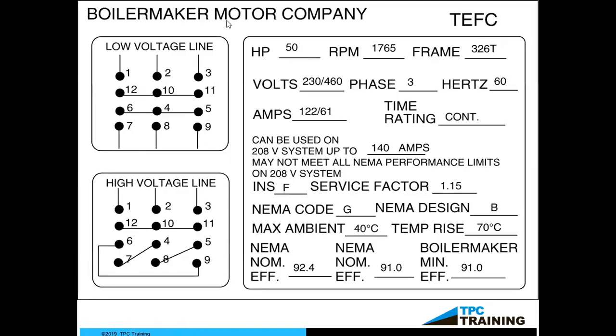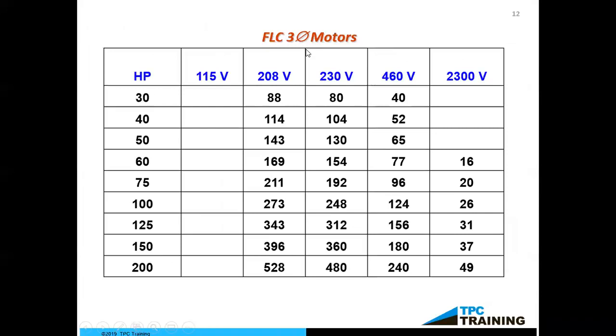So I did say that I wanted you to really think about this FLA, the 61 amps at 460 volts. Remember, it is a 50 horsepower motor, because the next slide that I have does not say FLA at the top. It says FLC. So the FLA that we saw on the motor, the 61 amps, that's full load amps, comes right off the motor nameplate. This is full load current, and it comes out of the National Electrical Code. This number will always be higher than the FLA that we see on the nameplate.